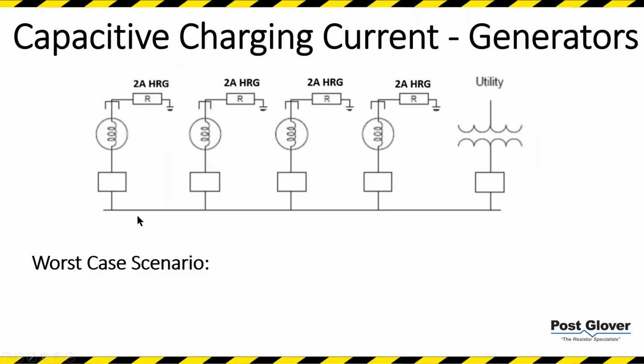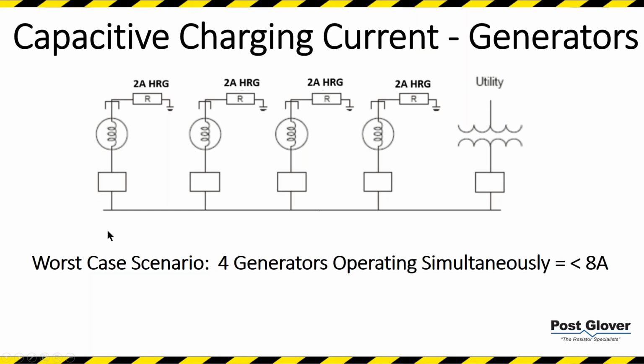Another thing to speak to: a lot of times we get in the situation where we have parallel generators and we're trying to figure out how to do the capacitive charging current. Just so you know, essentially ground fault current is additive when you parallel. So we're talking about overall systems of 8 amps. In this scenario, you have 8 amps of HRG ground fault current, and then your system's capacitance, or charge current, would have to be less than 8 amps, right?